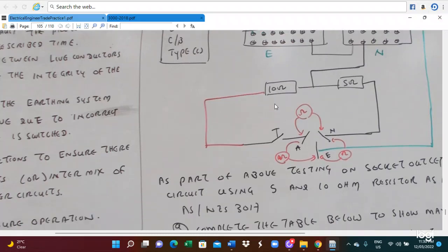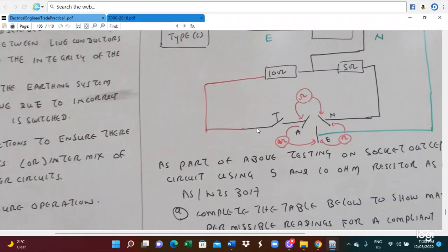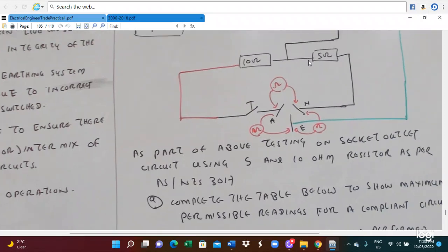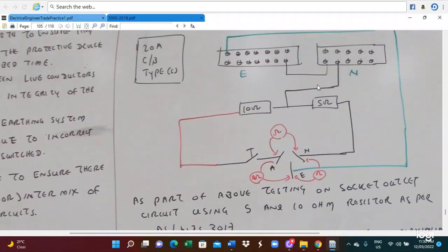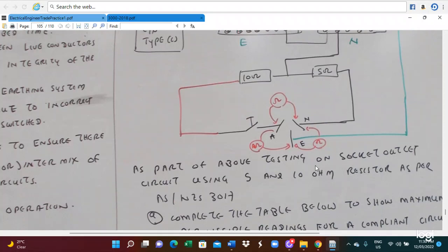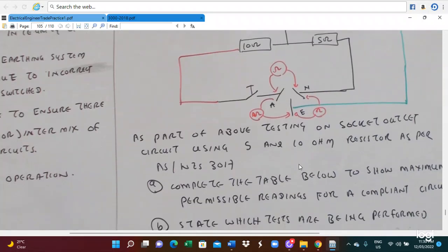This connection diagram shows 10 ohms here and 5 ohms there. Here is the neutral link and the earth link - we measure 10 ohms and 5 ohms resistance. This way we can measure polarity, according to the AS/NZS 3017 rule.